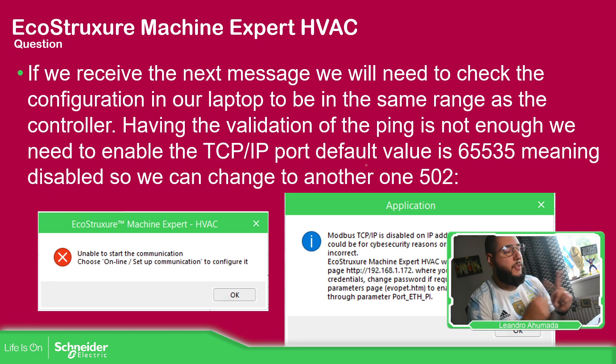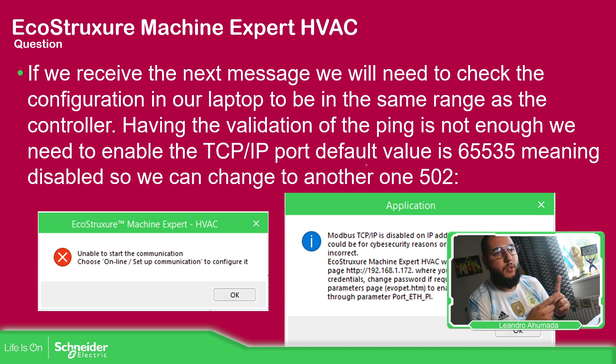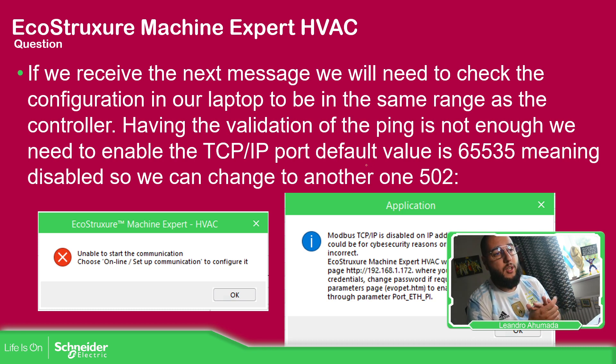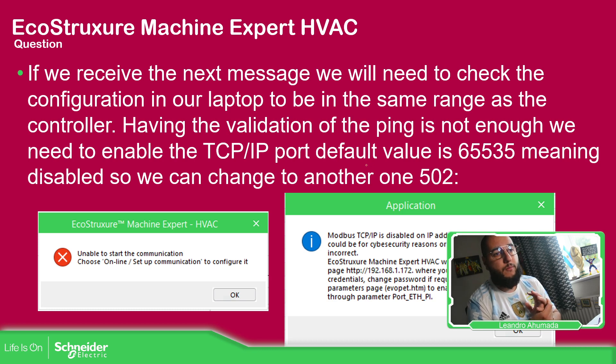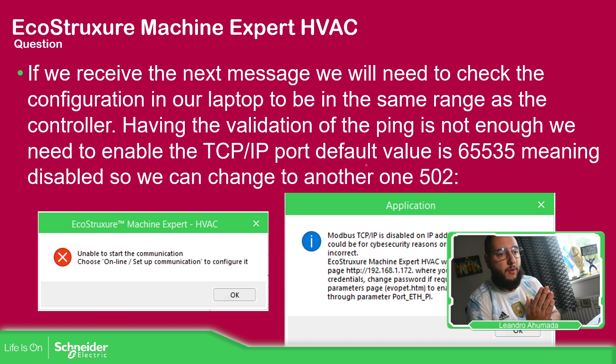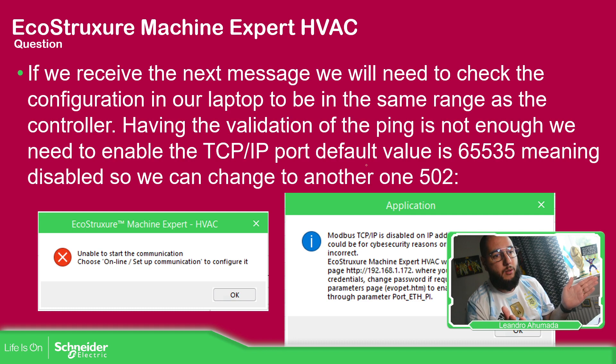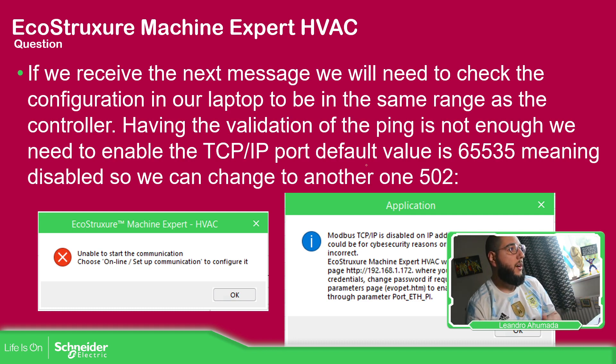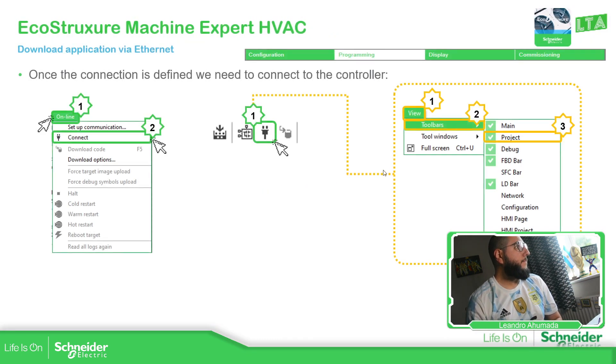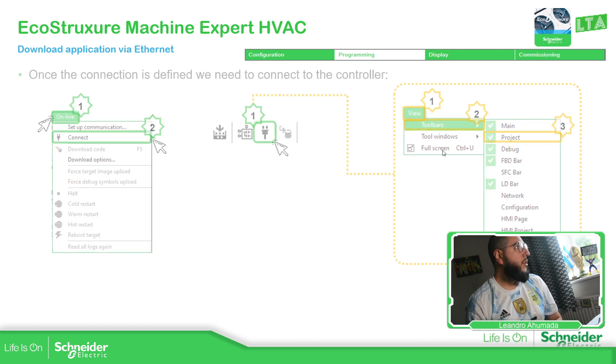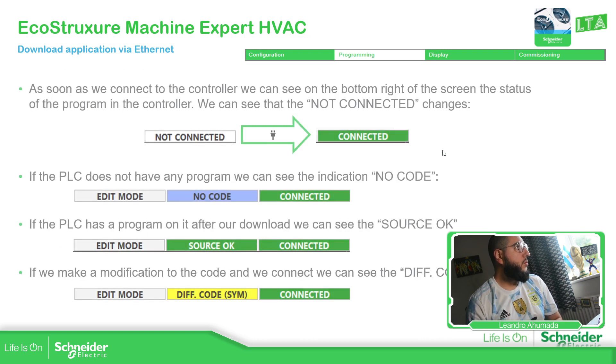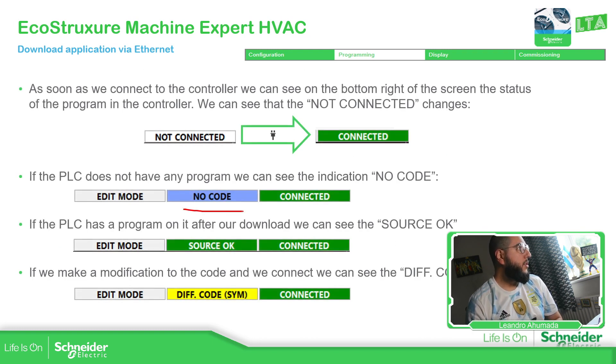So this is a message already explained to you. If you have this message before, we just need to change the TCP/IP value from 65535 to another value. The standard will be 502. Then we just connect to the controller.